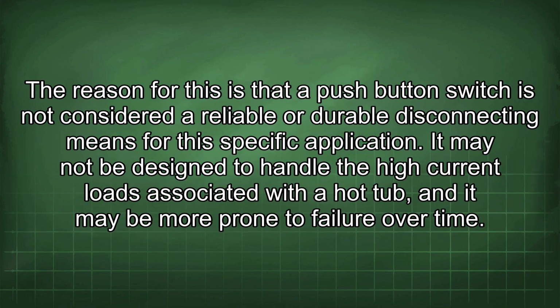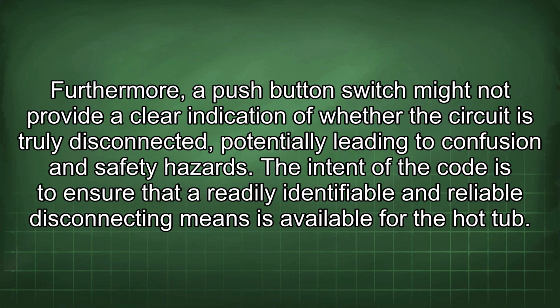The reason for this is that a push-button switch is not considered a reliable or durable disconnecting means for this specific application. It may not be designed to handle the high current loads associated with a hot tub, and it may be more prone to failure over time. Furthermore, a push-button switch might not provide a clear indication of whether the circuit is truly disconnected, potentially leading to confusion and safety hazards. The intent of the code is to ensure that a readily identifiable and reliable disconnecting means is available for the hot tub.